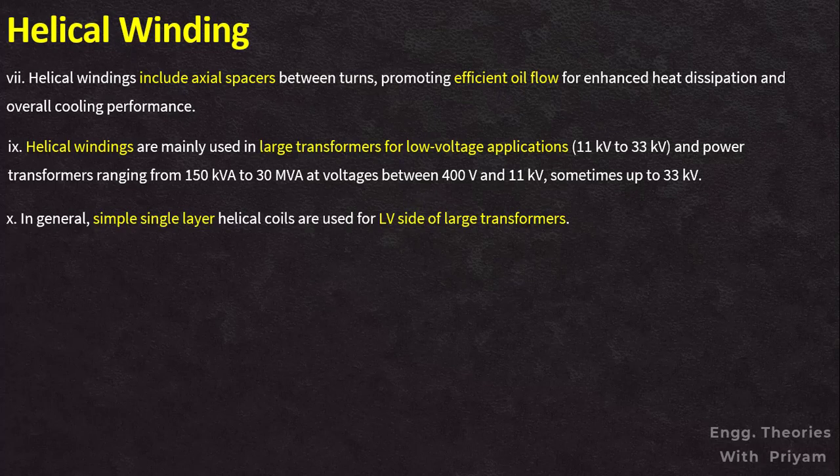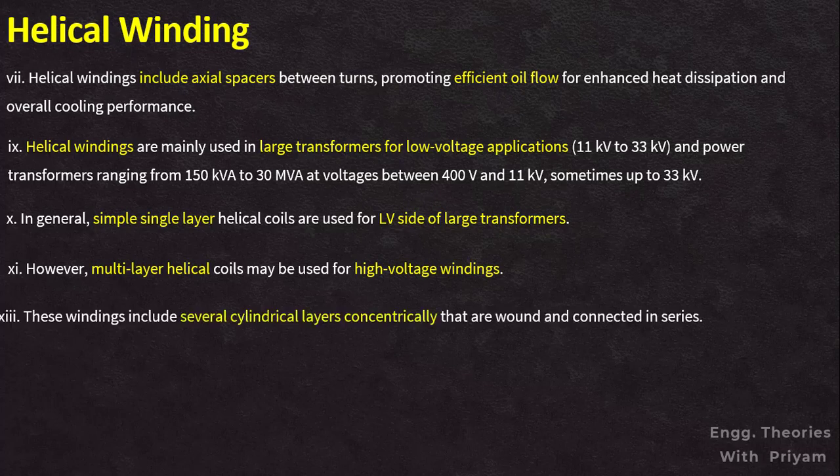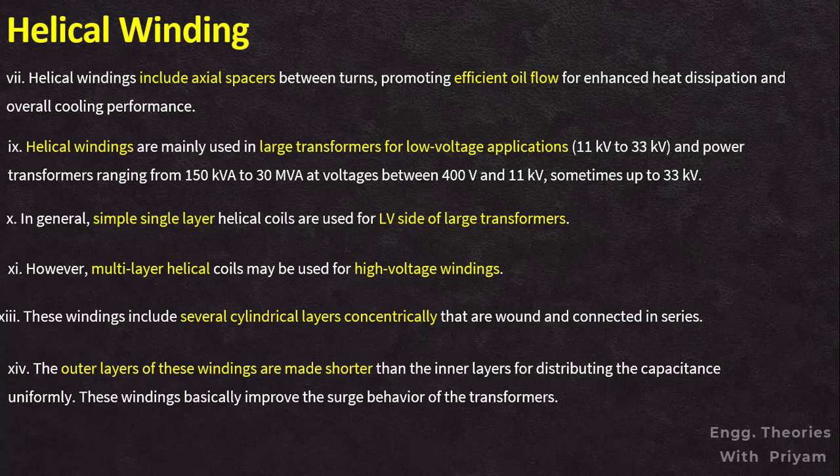In general, simple single-layer helical coils are used for LV sides of large transformers; however, multi-layer helical coils may be used for high-voltage windings. Multi-layer helical winding is commonly used for high-voltage windings, specifically at 110 kV and above. These windings include several cylindrical layers wound concentrically and connected in series. The outer layers are made shorter than the inner layers to distribute the capacitance uniformly, which improves the surge behavior of the transformers.